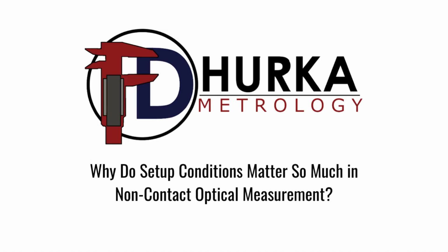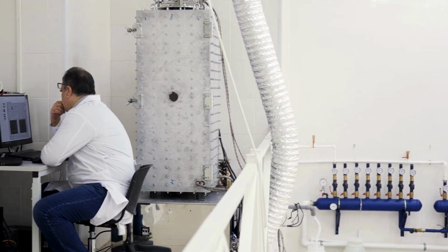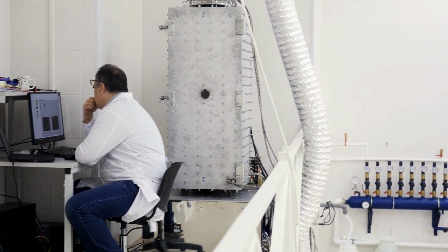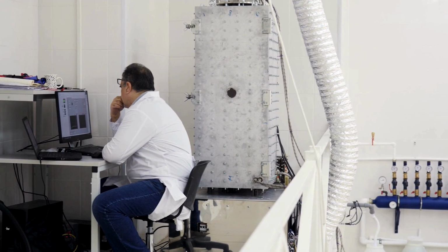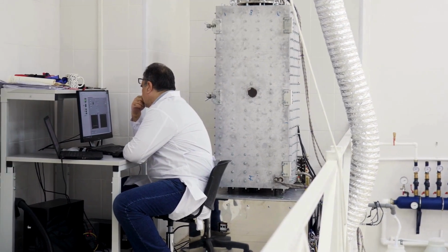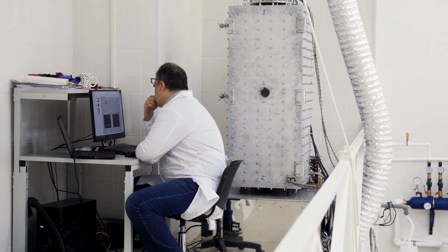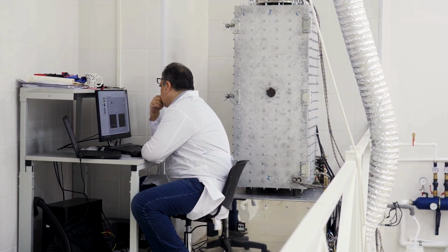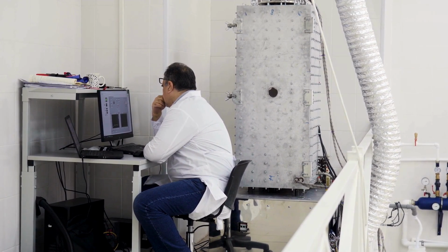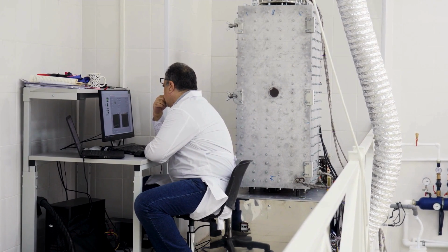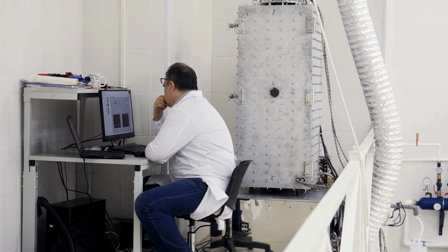Why do setup conditions matter so much in non-contact optical measurement? Unlike contact tools that measure what they physically touch, a vision measurement machine measures what the camera sees and what the software interprets, which means the optical path, the environment, and the calibration state of the system all become part of the measurement, and getting any one of them wrong will produce wrong numbers.